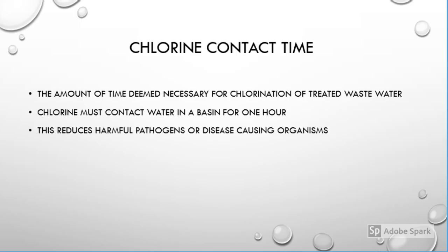The chlorine contact time in this particular system is 1 hour, which is sufficient to decrease fecal coliforms and other potential pathogens to acceptable levels. However, before release to the environment, the water in the chlorine contact tank must be dechlorinated, as chlorinated water can negatively affect natural water systems. The addition of sodium bisulfite before environmental release almost completely removes residual chlorine. The water that is being released to the environment must follow guidelines for acceptable levels of key pollutants or nutrients and is governed by the plant's license.